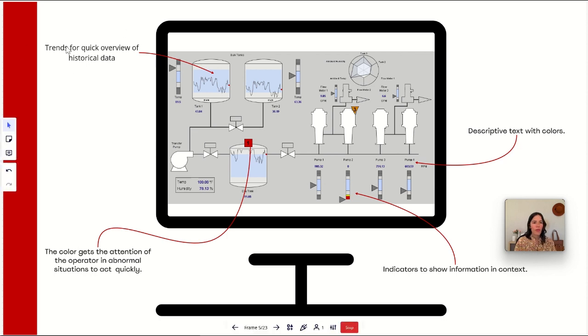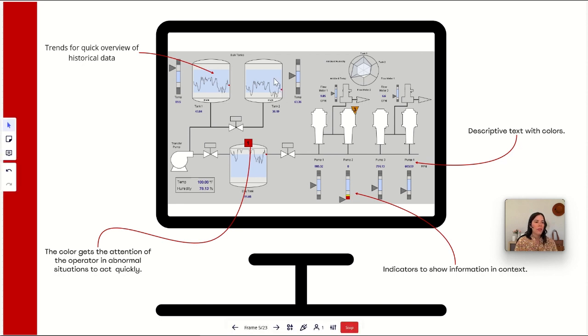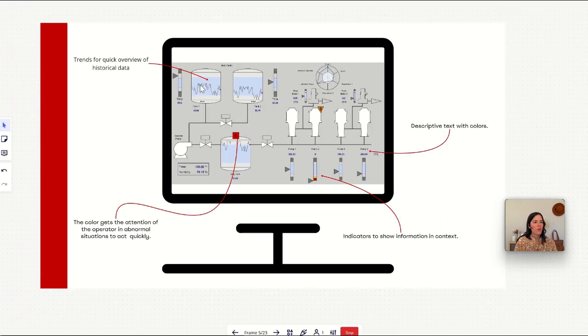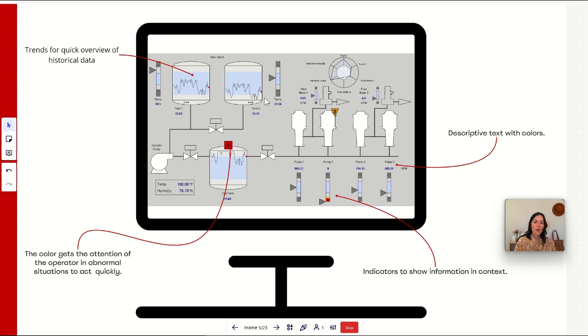Then we have trends for a quick overview of historical data. In this case, you can see that this trend is inside the blue frame, which means it is inside the desired values — everything is right. But here we can see the trend goes up and down and goes outside the desired value, so something is not right for this process value. We can see the same for this tank. Basically, a high performance HMI will look more or less like this, and the idea is that the operator can quickly see when something needs attention and act quickly.